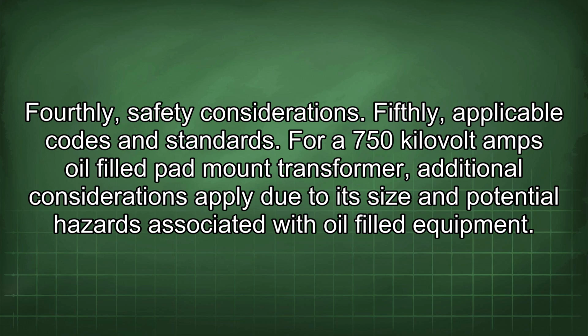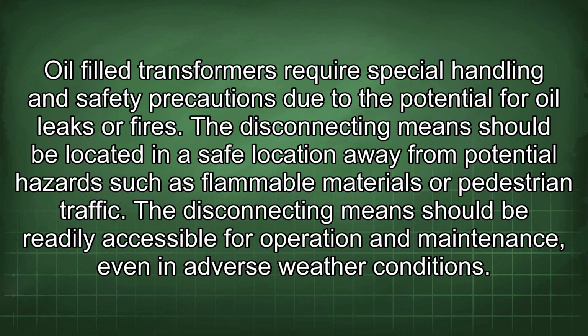For a 750 kVA oil-filled pad-mount transformer, additional considerations apply due to its size and potential hazards associated with oil-filled equipment. Oil-filled transformers require special handling and safety precautions due to the potential for oil leaks or fires. The disconnecting means should be located in a safe location away from potential hazards such as flammable materials or pedestrian traffic. The disconnecting means should be readily accessible for operation and maintenance, even in adverse weather conditions.